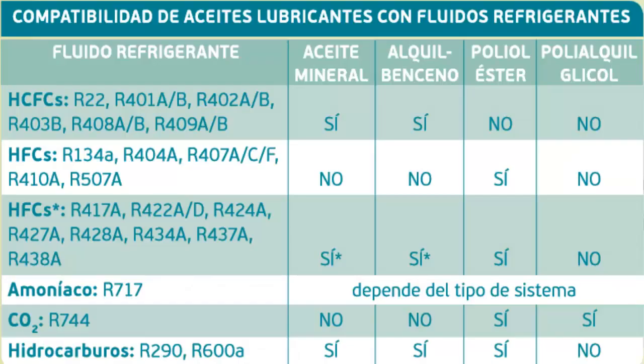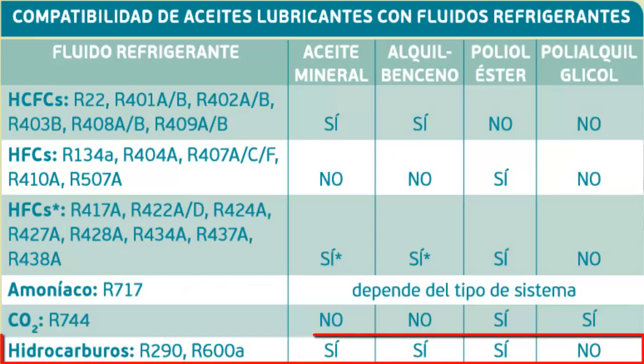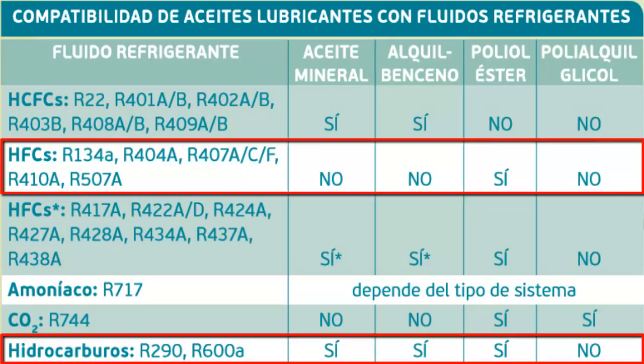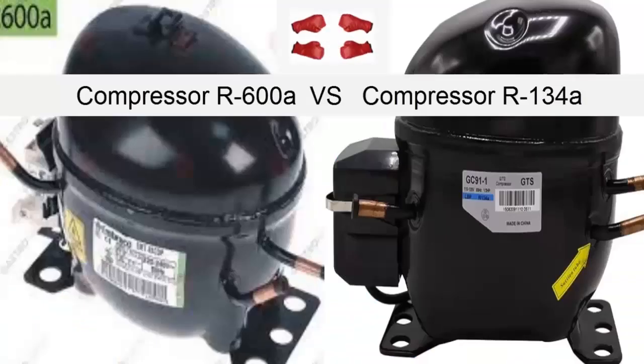As for oil compatibility, R600A is compatible with mineral oil, alkylbenzene, and polyolester oil (POE), while the R134A compressor only uses POE oil.